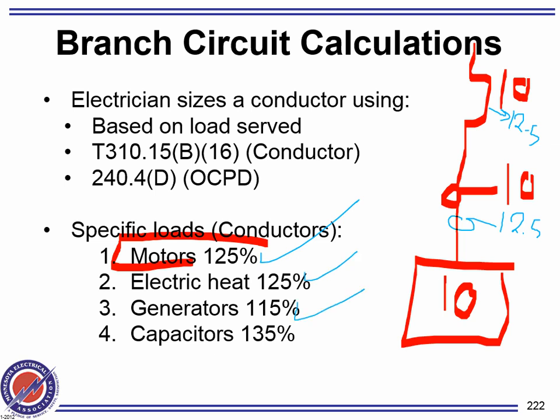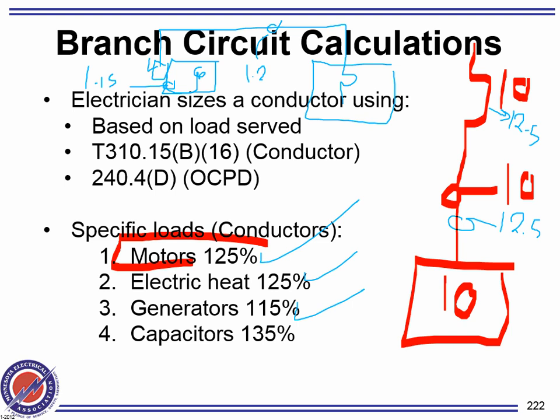Generators, guys, this is confusing. This is between the generator and the overcurrent protection device. So here's my fuse disconnect on the gen. From the windings into here, they allow you to size it based on 1.15. But from the breaker on the gen all the way to your service, where you bring your service to the auto transfer switch, this will be a continuous load, 1.25. Making sense?